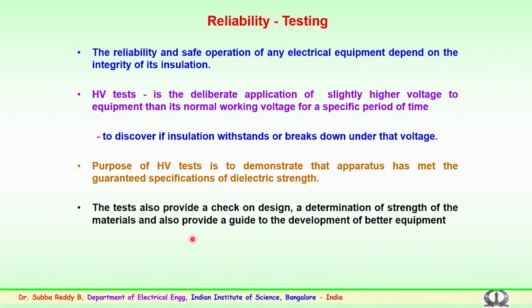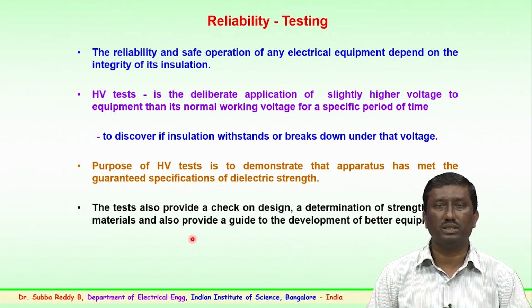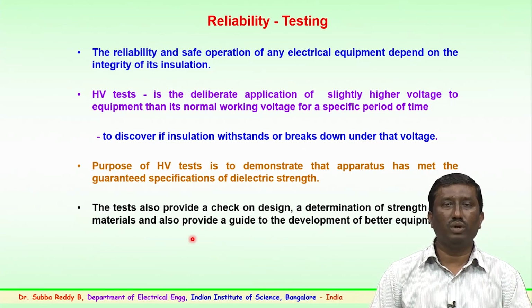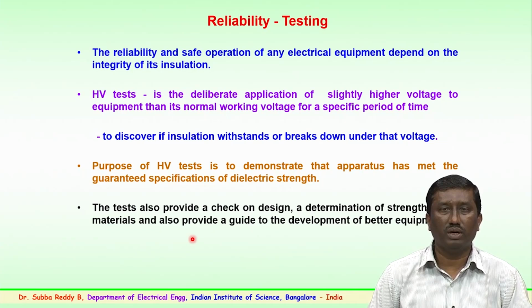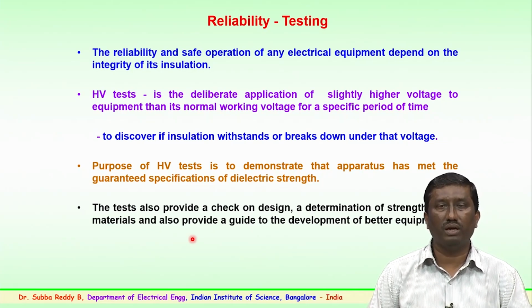So, reliability and testing is a very important aspect. Reliability becomes an important factor for the safe operation of any electrical equipment, which depends on the integrity of its insulation, for which it is designed. So, the high voltage test basically is an attempt to deliberately apply a slightly higher voltage to the equipment than its normal working voltage for a specific period of time.